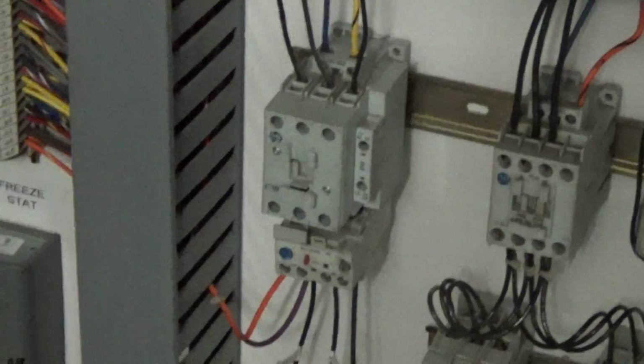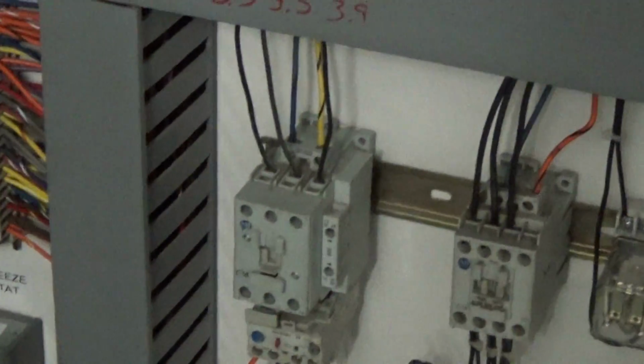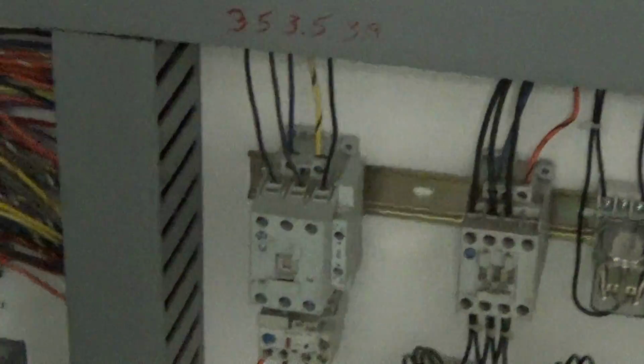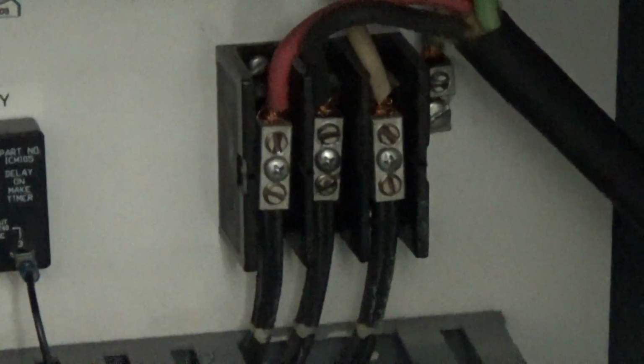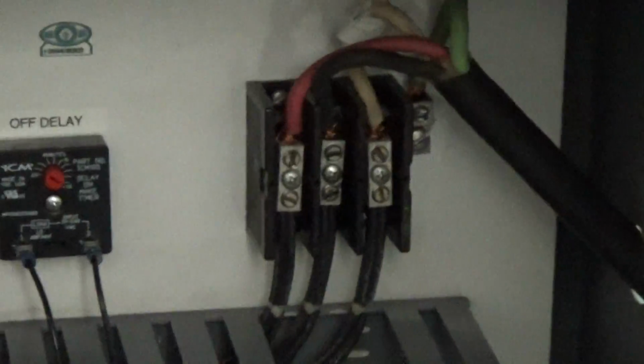If it's rotating the other direction, do not change any wires on your contactors or overloads or whatever, because that's all synchronized with the compressors and the blowers. What you want to do is turn off your main power, and probably the easiest thing to do is swap any one of those two hot leads going into your incoming power there.